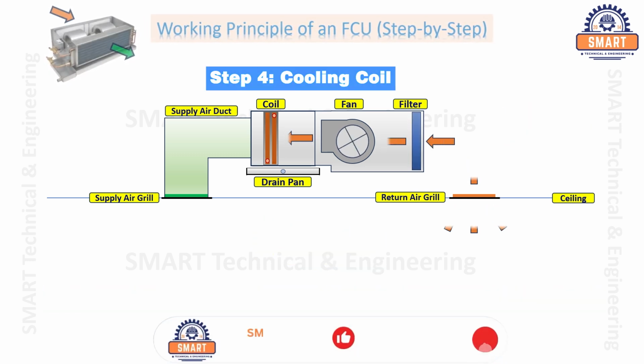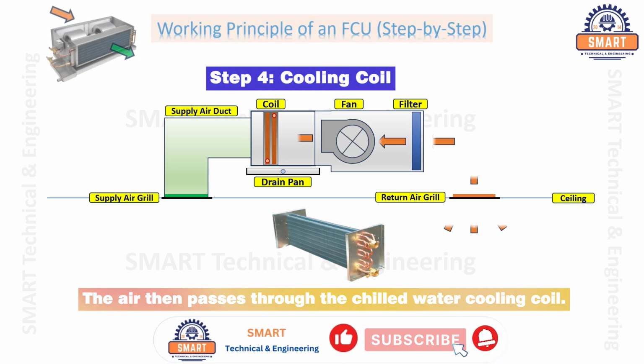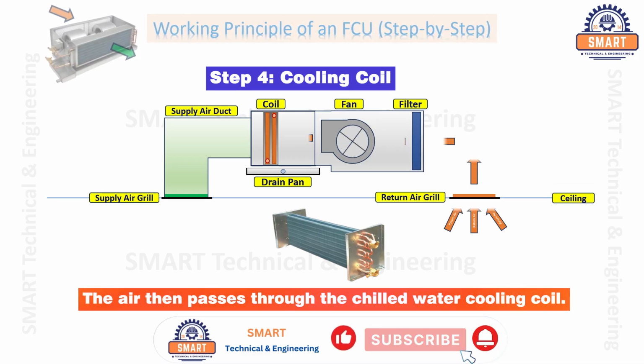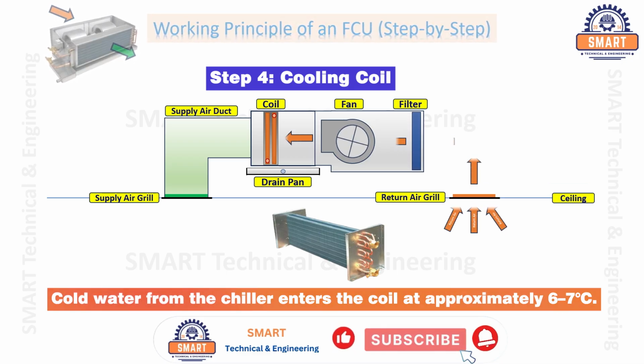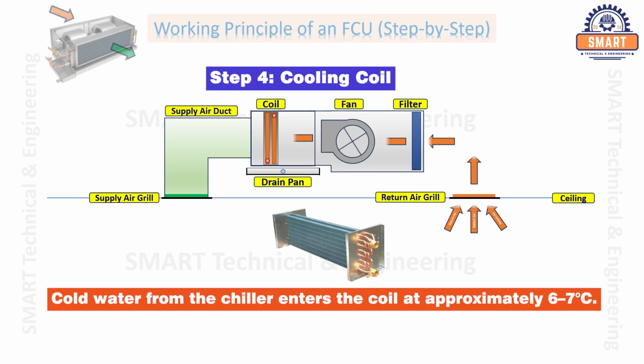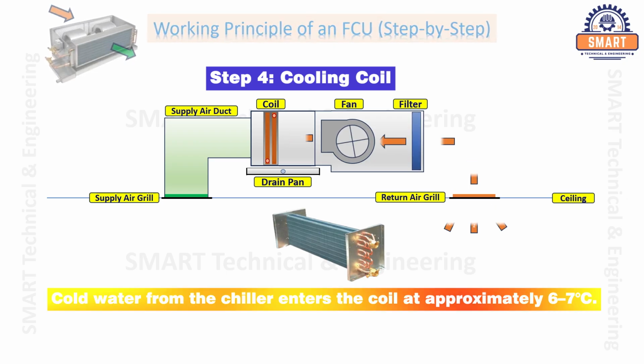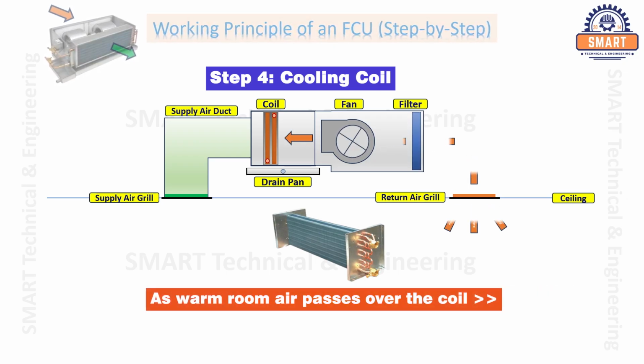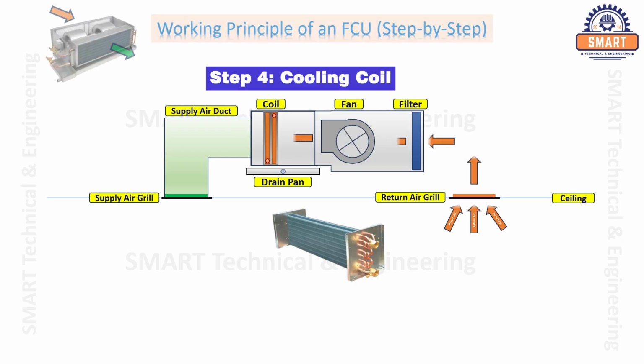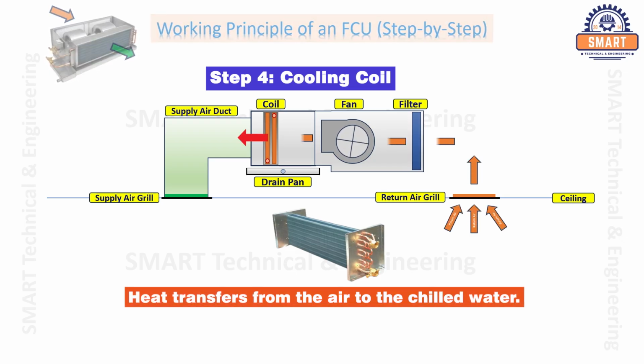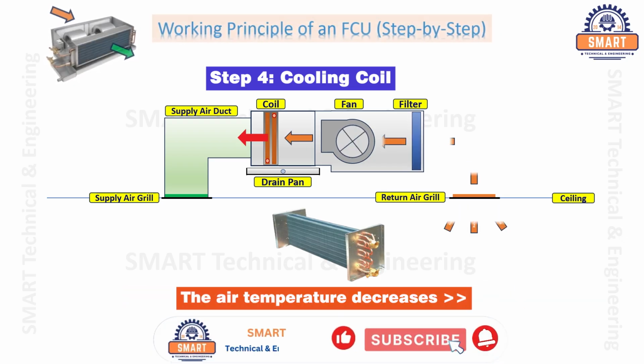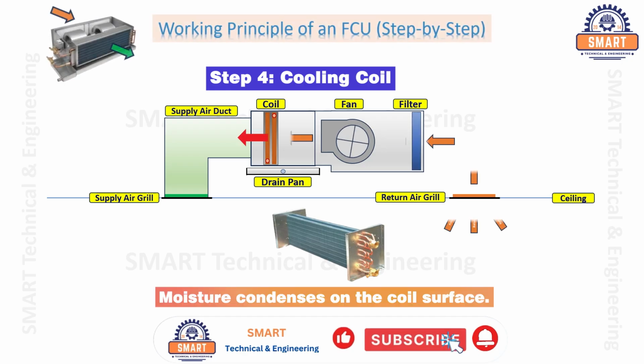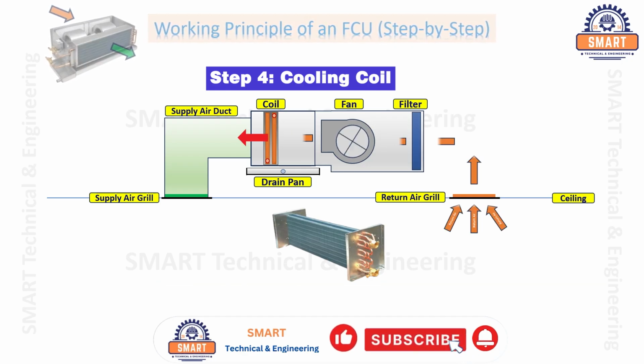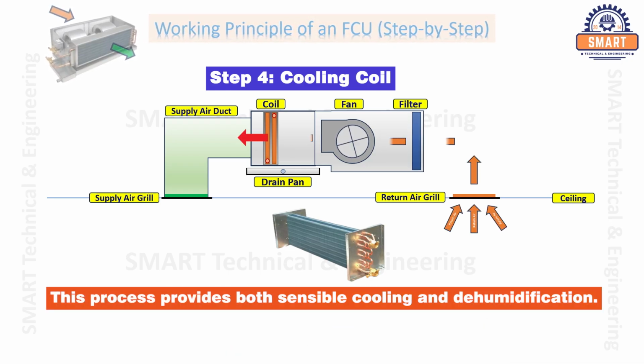Step 4. Cooling coil. The air then passes through the chilled water cooling coil. Cold water from the chiller enters the coil at approximately 6 to 7 degrees Celsius. As warm room air passes over the coil, heat transfers from the air to the chilled water. The air temperature decreases, and moisture condenses on the coil surface. This process provides both sensible cooling and dehumidification.